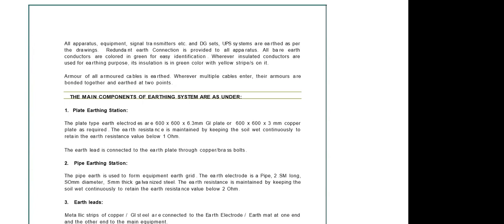Generally, as I said, in big infrastructure type jobs we use a huge earth electrode, but for smaller jobs this big earth electrode is not required. Again, there is a calculation for the dimension of the particular earth electrode. It comes from the fault level calculation. So in addition to that big main earth terminal, we provide plate earthing stations. This is generally followed where space constraints are there, and for buildings, the hospital sector and this type of application, plate earthing is very popular.